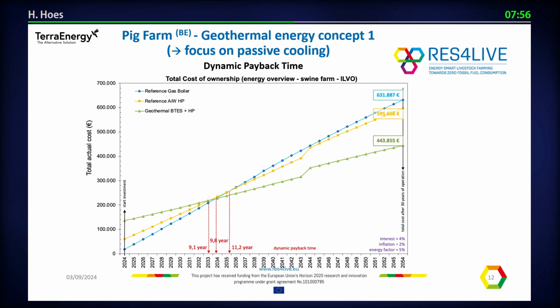You can also do a total actual cost or the total cost of ownership calculation. It's not so difficult to see what's meant in this graph. In the beginning, on the left, you see the initial investment. Of course, the initial investment for the geothermal is the highest. The air-water heat pump is a little bit between, and the gas boiler is the lowest, the blue one. But of course, the blue one will have a higher energy price every year, and the green one the lowest. And then you see, of course, the intersection that gives you some sort of dynamic payback time between 9.1 and 11.2 years, with a given interest, inflation, and energy factor rates, which are, of course, not always for everyone the same. And in total, after, in this case, 30 years, you have a total expense of the numbers you see here.